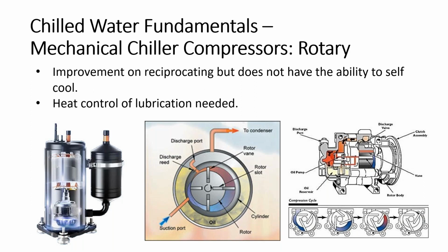An upgrade also some years ago was the rotary. The rotary basically has one rotating cylinder inside another cylinder with these vanes that compress and isolate the low side from the high side. One of the problems, though, is the whole compressor is on the high side, and so they get very hot. So the early versions had trouble maintaining lubrication because it got so hot. The outside of the case, you couldn't put your hand on it.